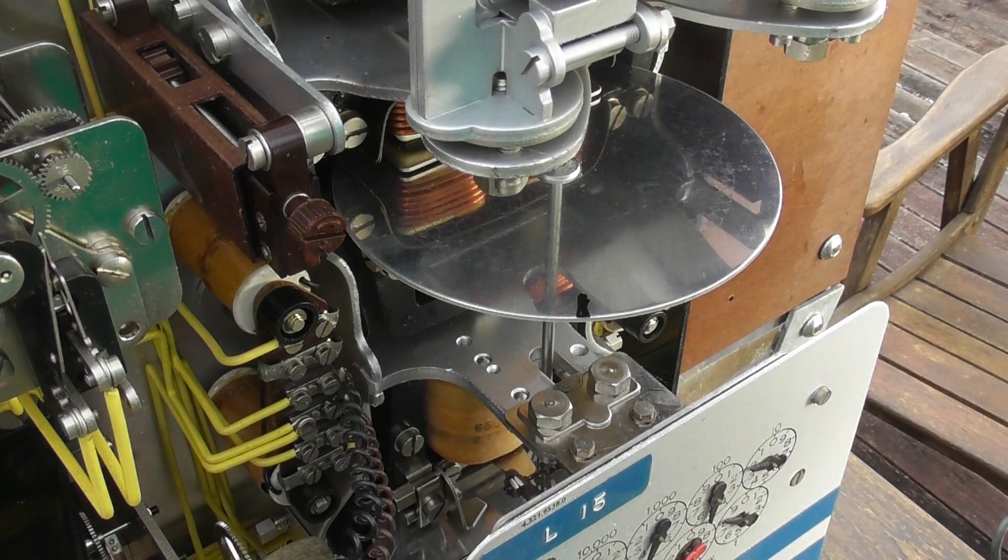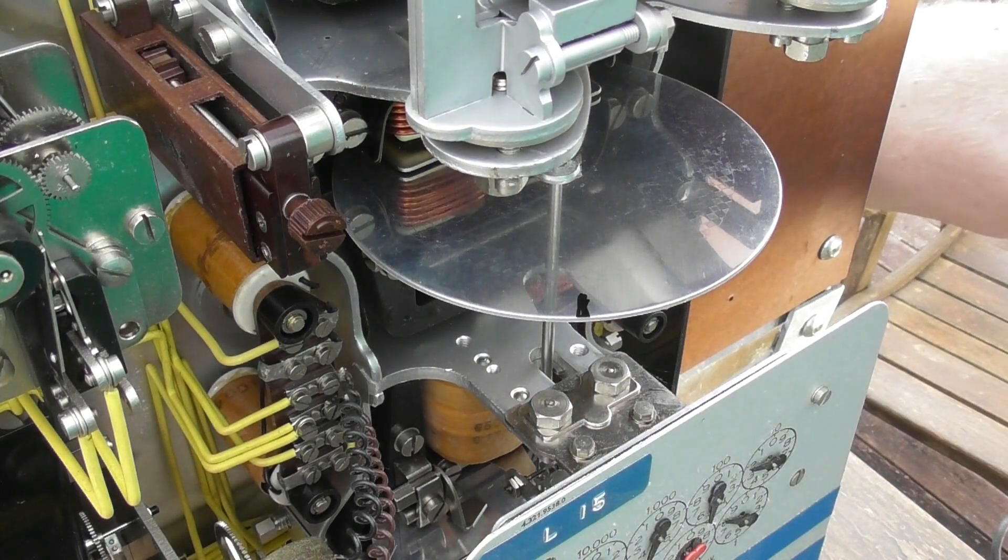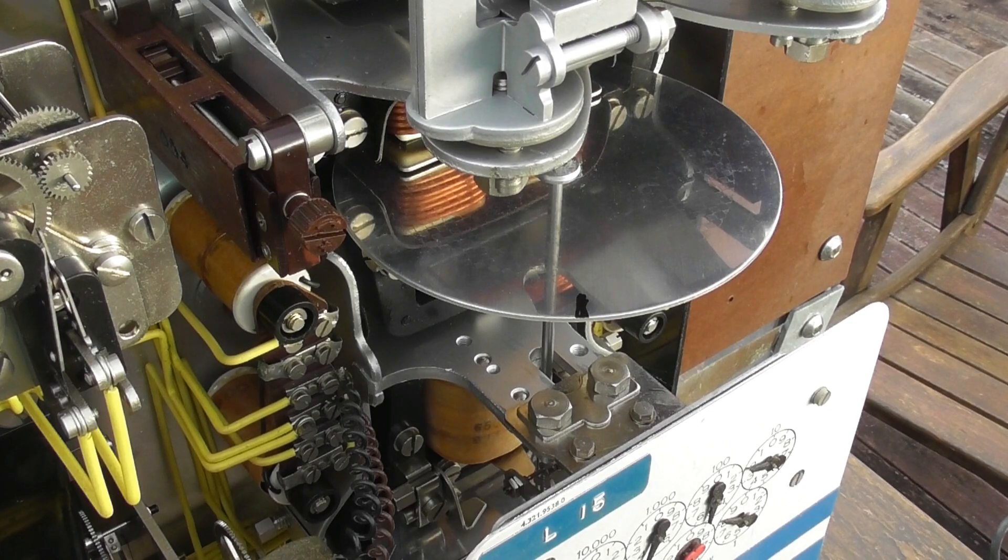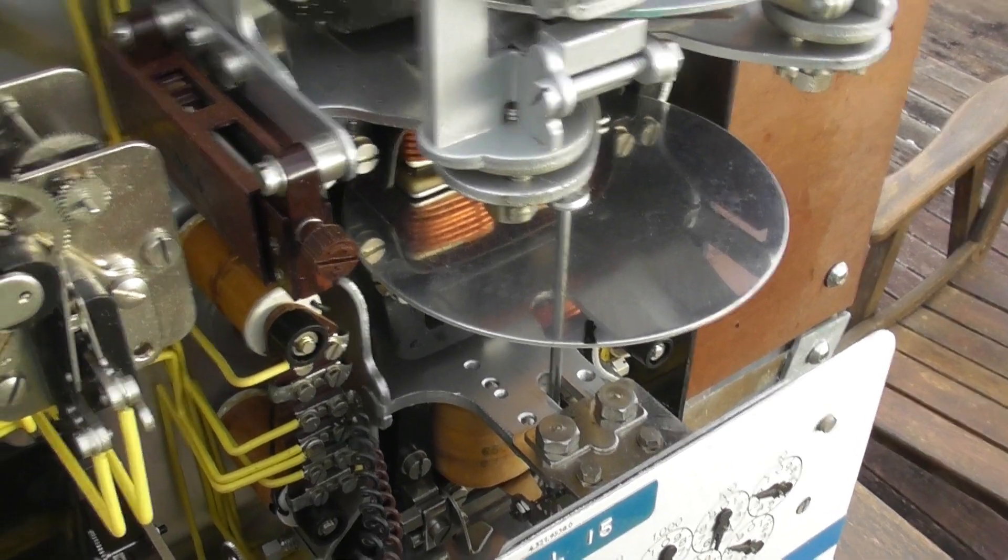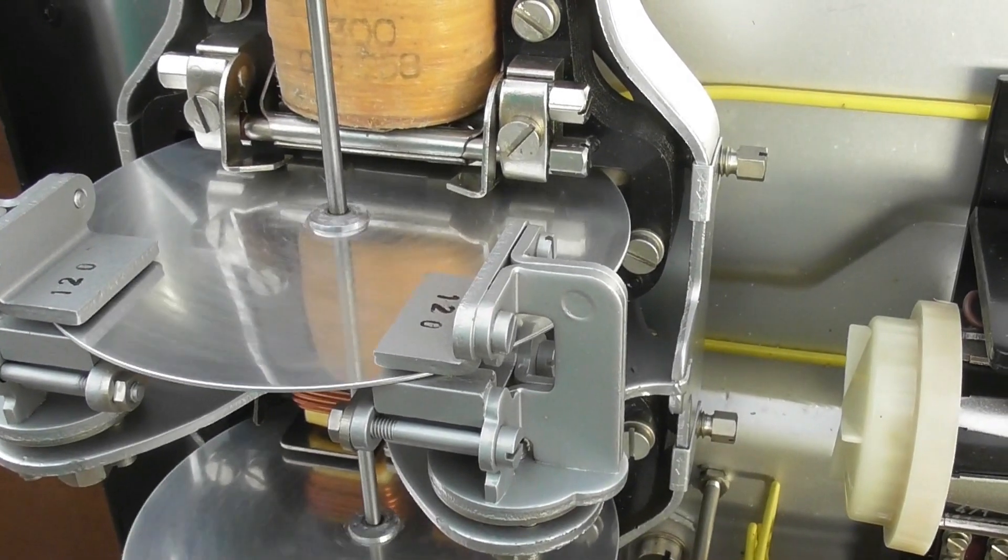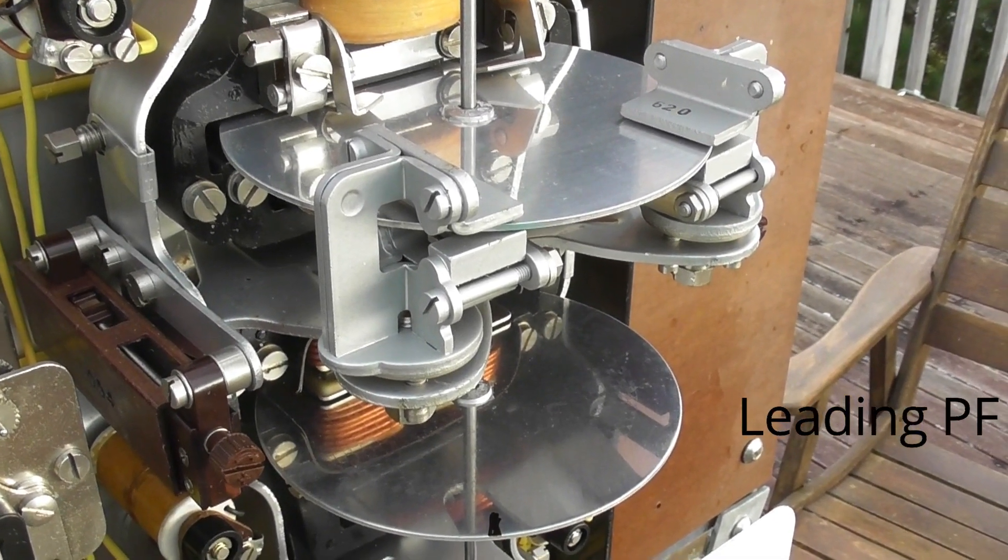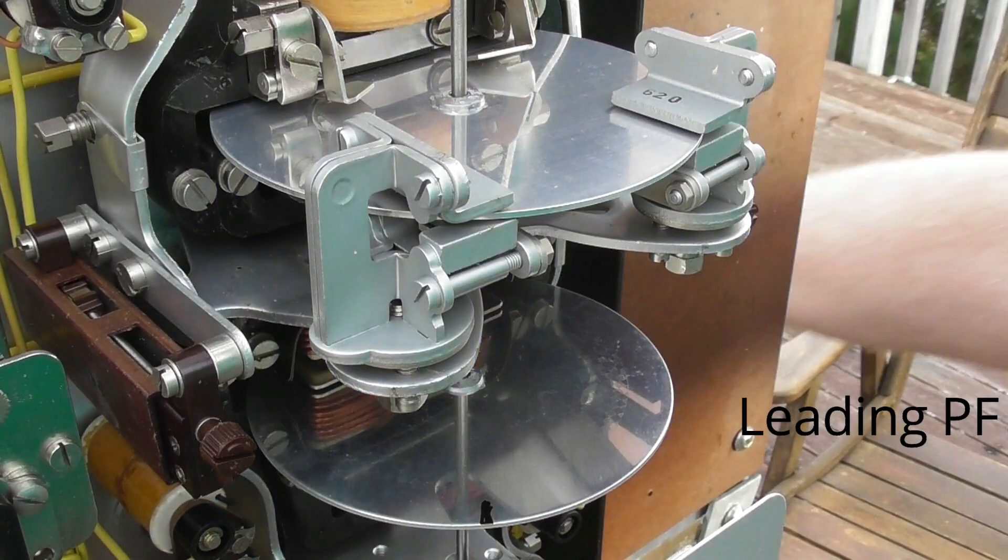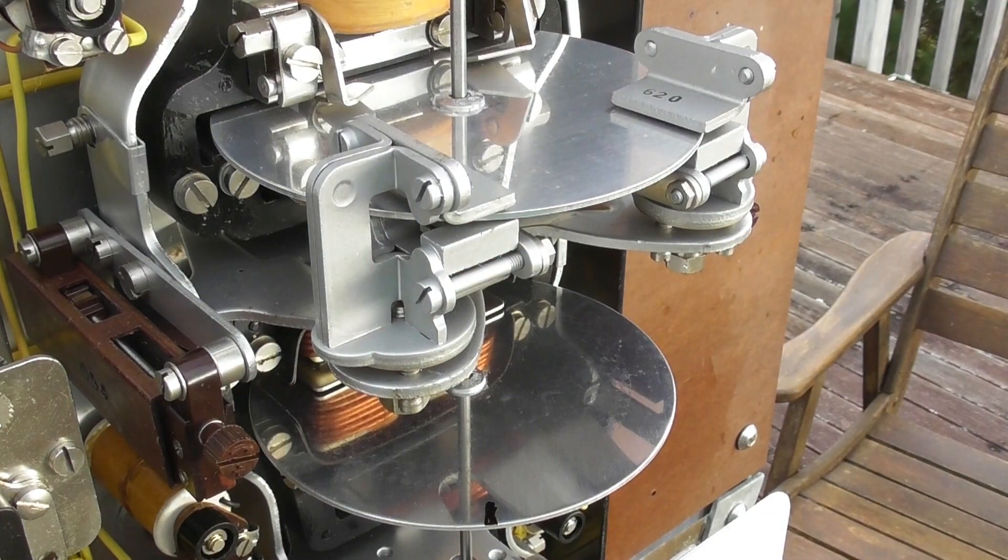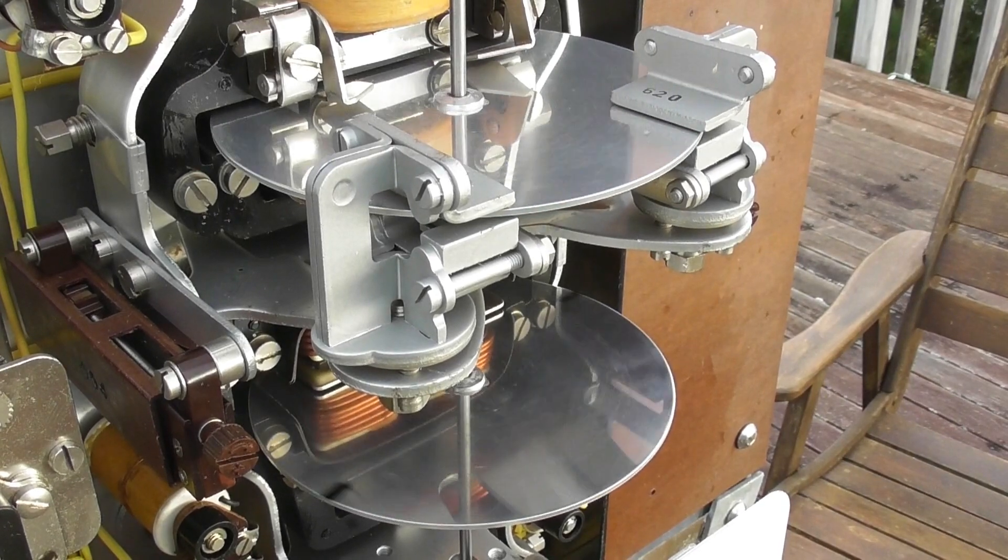Now, say the factory decided to turn heaters on. I'm going to add a resistive load, see if it makes any difference. Now, the active meter is turning. So we have exceeded the power factor in this particular situation. What I'll do, I've got 60 micro, I'll make it 45. Unplug the capacitors. There we go, the meter is turning again.